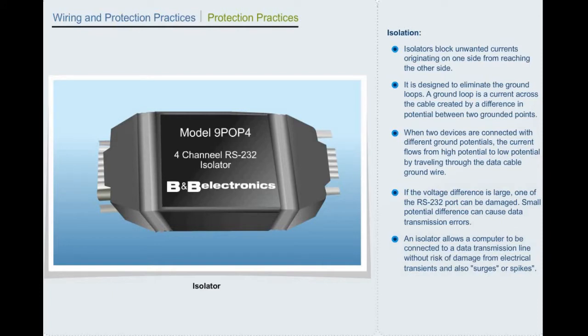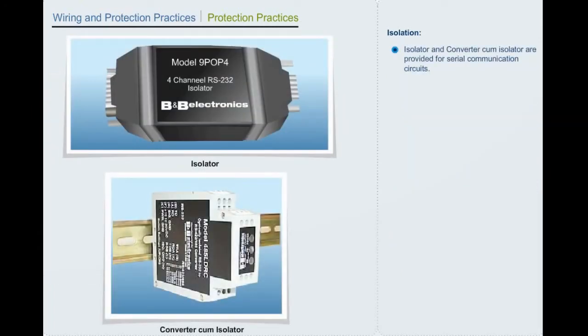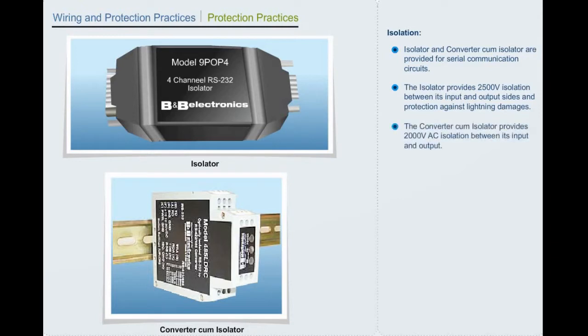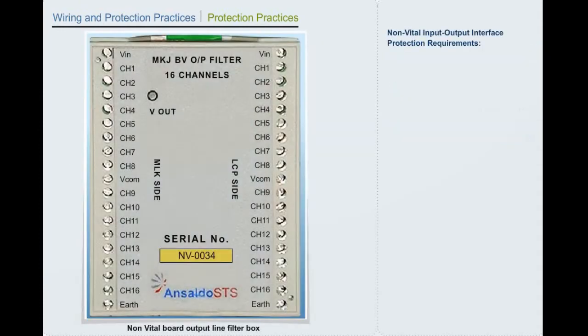An isolator allows a computer to be connected to a data transmission line without risk of damage from electrical transients and also surges or spikes. Isolator and converter-cum-isolator are provided for serial communication circuits. The isolator provides 2500 volts isolation between its input and output sides and protection against lightning damages. The converter-cum-isolator provides 2000 volts AC isolation between its input and output.